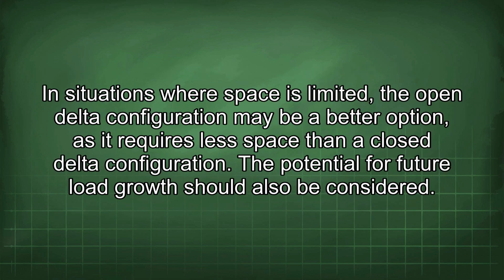The physical space constraints for the transformer installation can also be a factor. In situations where space is limited, the open delta configuration may be a better option, as it requires less space than a closed delta configuration.